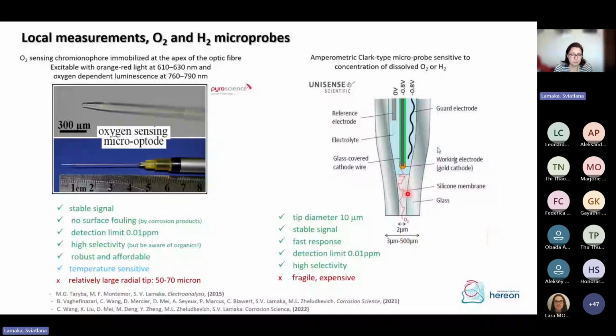Now, the unique feature of the equipment that we have is that we integrated all these commercial microprobes from Unisense, which is pH, oxygen, hydrogen, or from Pyroscience, into our SVET equipment so that we can correlate the position of the probe with its readings. And this is very important because otherwise, neither Unisense nor Pyroscience, at least to my knowledge, provides any means to correlate probe position with its signal.